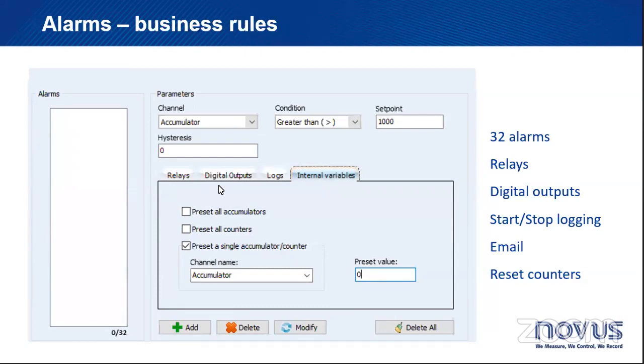Okay, I understand there is an integrator function in the virtual maths channel. What are the practical limits? I mean, the accumulation function. Well, it's completely feasible if, besides a pulse input, you have a 4 to 20 milliamps input on the field logger. When you have a 4 to 20 milliamps input, that means you already have flow data, so you're reading flow. In order to find out about the volume and totalize it, you want to accumulate, or integrate, that value.